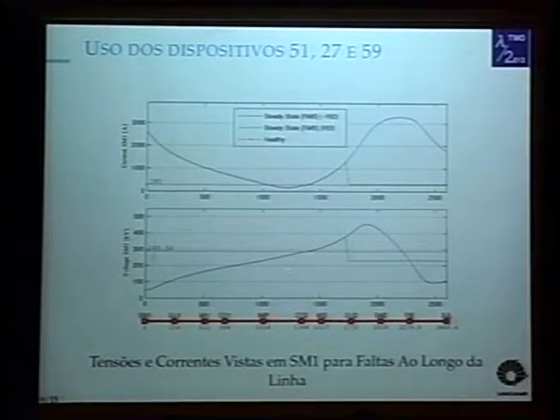The voltage continues to rise until reaching a point where we have a fault and the voltage is the same as the voltage without the fault. And then the voltage found in Serra da Mesa 1 when we have a fault, here after half the line, is larger than what the voltage without fault would be. So in blue it continues to increase until it drops again in the final segment. We saw that the reduced insulation distance held the voltages in this segment to these values you can see in green. So this is a specific behavior for this type of line, looking at the voltages.